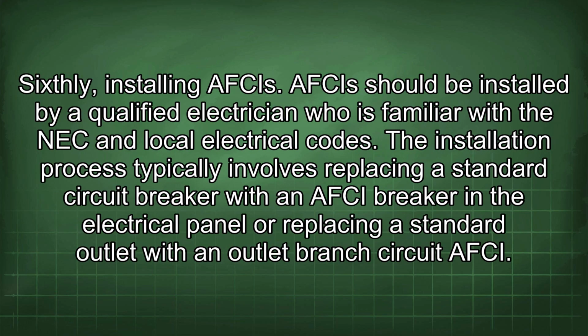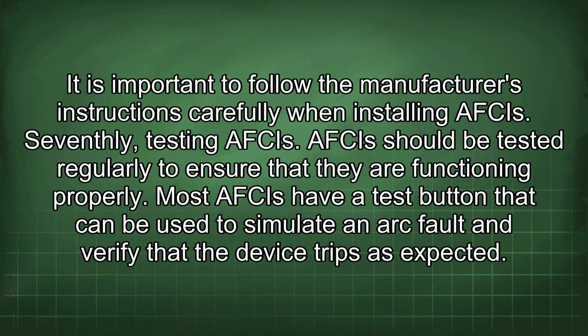Sixthly, installing AFCIs. AFCIs should be installed by a qualified electrician who is familiar with the NEC and local electrical codes. The installation process typically involves replacing a standard circuit breaker with an AFCI breaker in the electrical panel or replacing a standard outlet with an outlet branch circuit AFCI. It is important to follow the manufacturer's instructions carefully when installing AFCIs.